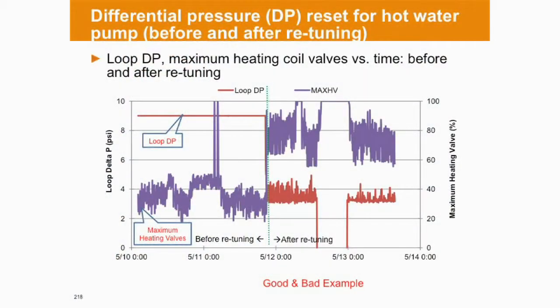So looking at this chart right here, the red line is the loop differential pressure, based on the left axis. The right axis is the heating valves, the maximum heating valve position. So this might be from a building that's got 100 reheat valves. And so what we see is, based on the DP setting of 9 PSI, the red line, that the maximum heating valve, based on the right axis, is running right about 45% open.